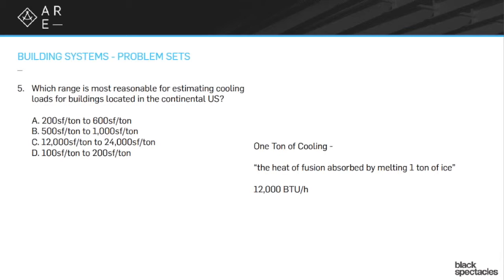Same square footage, but different use, different cooling needs — I would range it back and forth within that range. There's nothing sacred about these numbers. They're just the general rule-of-thumb numbers that most people would have at their fingertips when talking about these things. I always just remember 300 personally and use that, then let some engineer figure it out for me — but it always gets me in the ballpark. The 200 to 600 range, you can see how you could adjust it to the situation.